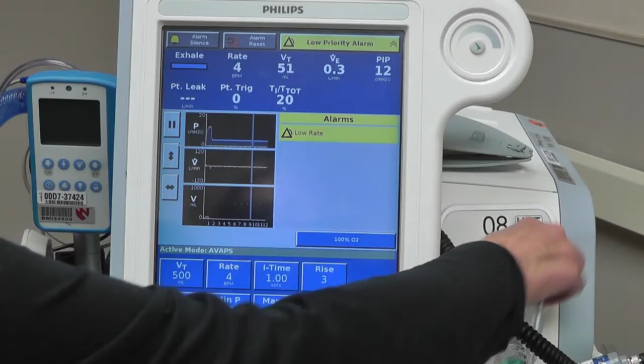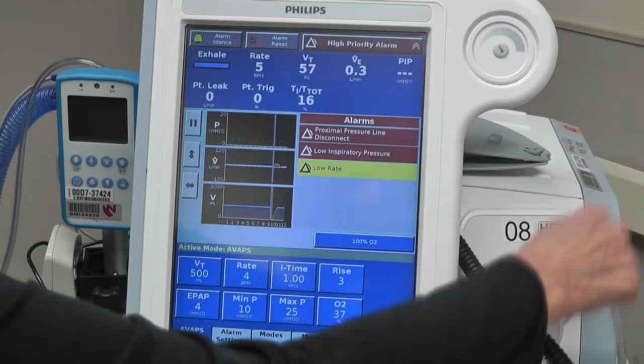and then we'll troubleshoot it. One of the things that can happen is this pressure line can become disconnected. There we go. We usually get a low priority alarm first, and then it will be a high priority alarm saying the proximal line has been disconnected. So there's our proximal pressure line disconnect. If I don't solve the problem, the alarm continues. But if I can discover what the problem is and reconnect the line, then the alarm will stop. So if it's something like that that you can quickly identify and troubleshoot and reconnect, then you've solved the problem and you don't have to take your patient off the machine.